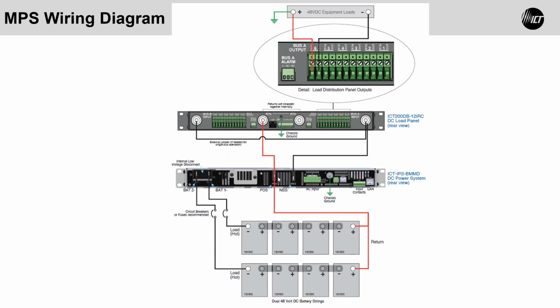So the plus side is going to be the return. The load is going into the input of the distribution panel, and they're jumpered together between bus A and bus B, so this entire panel is going to be neg 48. The return, since these are connected internally, comes back and connects to the positive terminal of the rectifier. When connecting the loads through the distribution panel, the output goes to the negative terminal of the device, and the return, referenced to ground, goes into RTN return. It's pretty hard to get wrong, but we want to make sure all the bases are covered and everything is clear. The important thing is to determine the requirement of the load device—the radio, the switch, the router, whatever you're powering—and what the polarity requirement is for it.